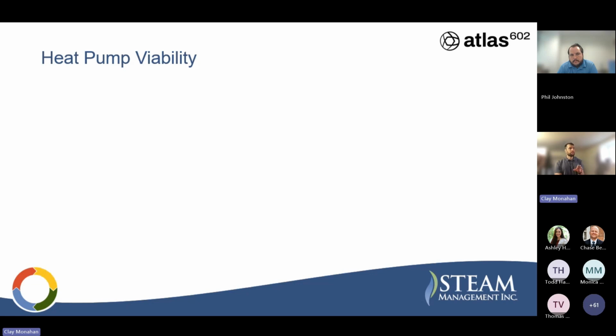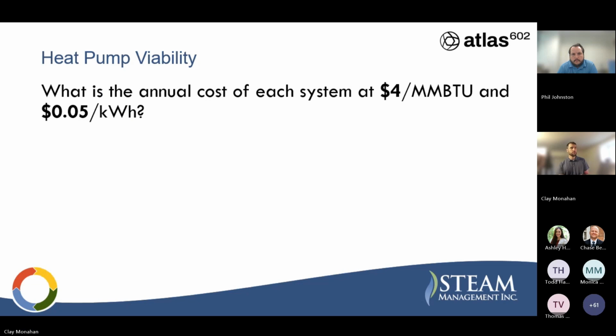All right, so let's keep the heat pump metrics the same on the temperature side, but change the energy pricing. So if we have $4 an MMBTU and 5 cents a kWh, so if you're down in Texas or something like that, where you're not natural gas distribution constrained, like we'll see on the next slide, and on your electricity, you have the ability to go out and get an energy supplier that could do some hedging and some stuff to actually bring your electricity cost down into this 5.5, maybe even 6 cent realm. But let's use 5 as the example, just as a sort of conservative case.